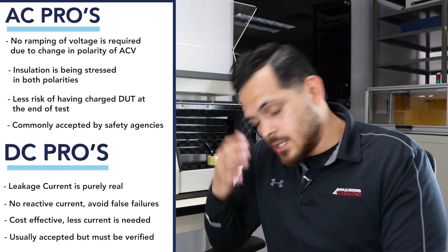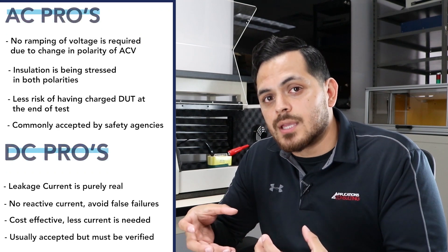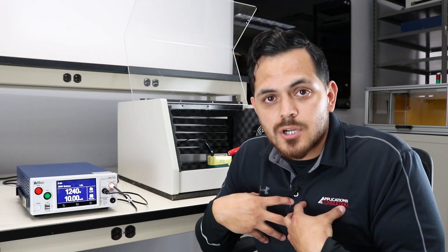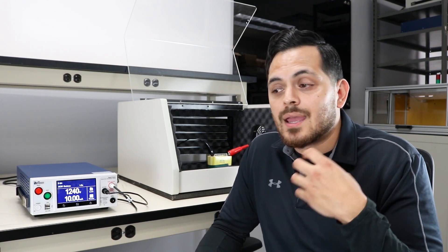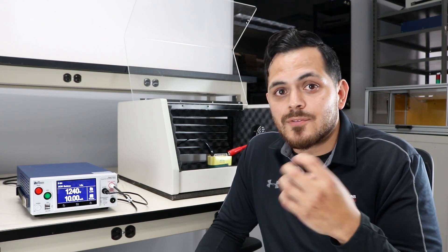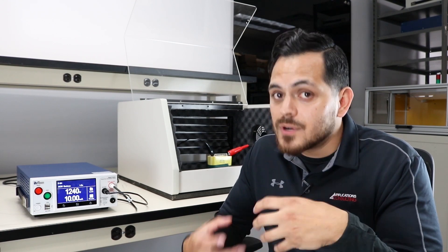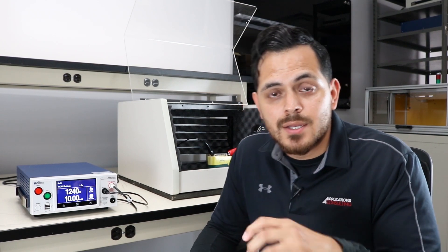Now we do have some redundancies built in - we will discharge the product at the end of the test - but we have a capacitive load spec. Not a lot of people look at that. If you're within a certain microfarad range and you're testing over a certain voltage, we can't guarantee that we're going to fully discharge that product. That's called our maximum capacitive loading in DC spec. That's something you want to look into if you're going to choose to run the DC hypot test.